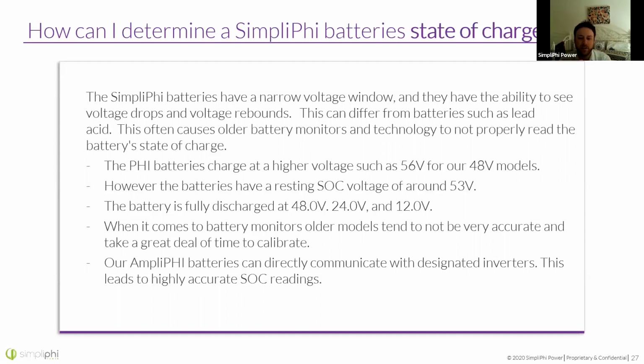When it comes to battery monitors, older monitors tend to be very inaccurate and take a great deal of time to calibrate, depending on the exact monitor you're using. No matter what, they'll take a while to calibrate, and any accurate reading requires precision-based set points, which we typically include in our integration guides. So for a Schneider battery or battery monitor kit, you can go into our integration guide for Schneider and see exactly what we recommend the set points to be.